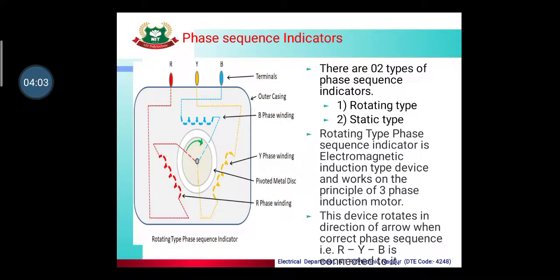Moving on to the second indicator — the phase sequence indicator. This indicator shows the phase sequence of the three phases: R, Y, and B. The correct phase sequence is R-Y-B. If any phase is interchanged — such as Y-R-B or B-Y-R — that is a reverse phase sequence. There are basically two types of phase sequence indicators: rotating type and static type.